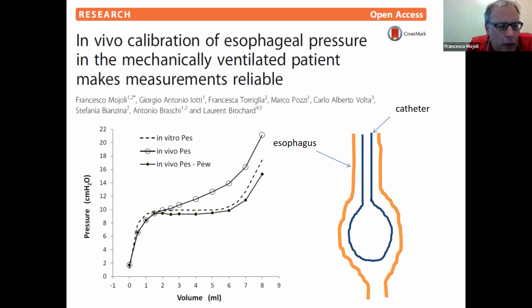If you manage your catheter manually, it is not possible to have the balloon continuously inflated, because the balloon is spontaneously and slowly deflating. So every time you approach the patient and want to perform a new measurement, you have to reinflate the balloon. Okay. If you have a dedicated monitoring system able to reinflate the balloon periodically, this is okay. It's not injuring the esophagus anyway.